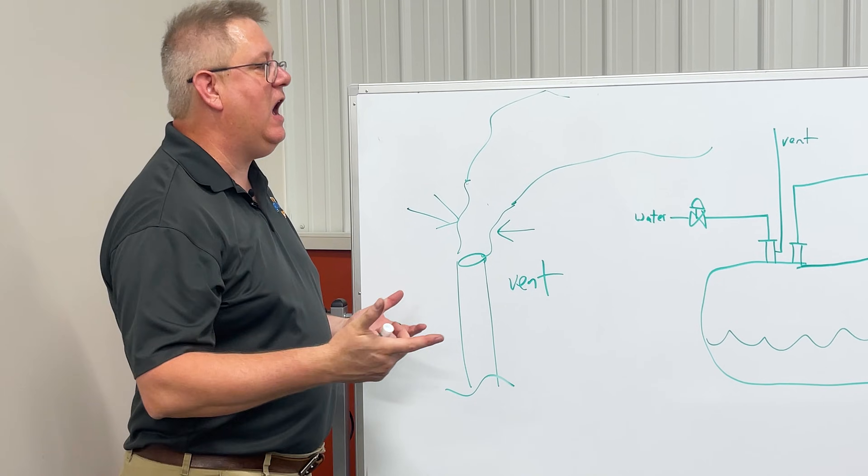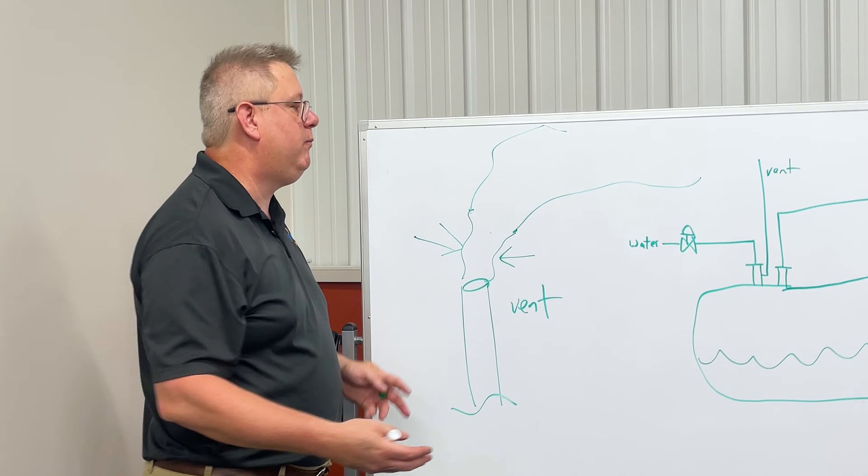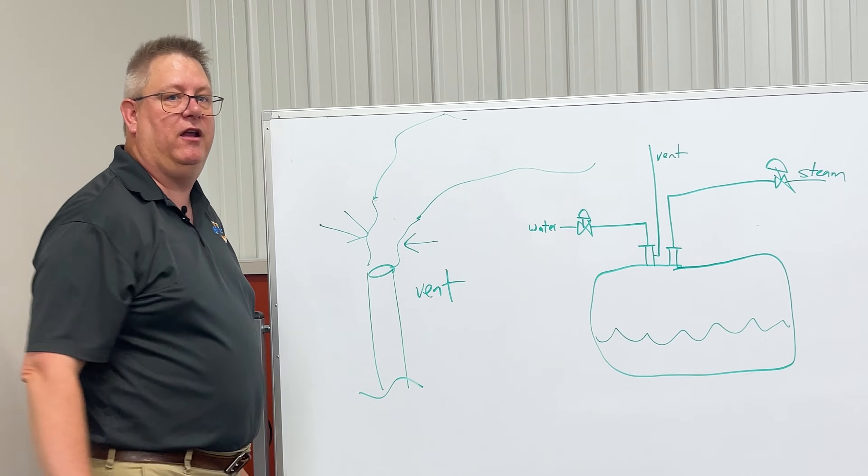But if our deaerator temperature's dropping even though we're maintaining pressure, we may have to crack that vent a little bit more.